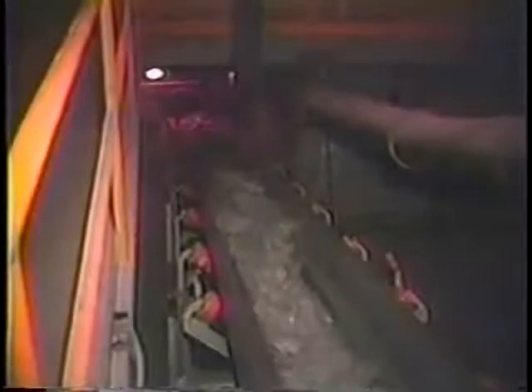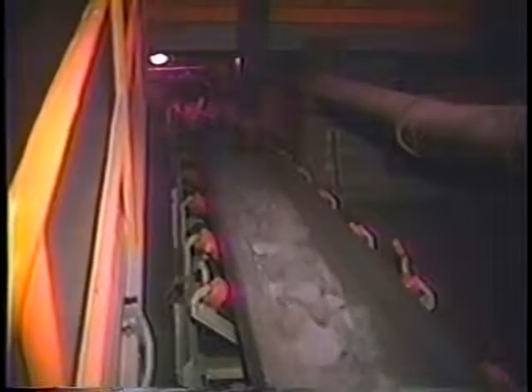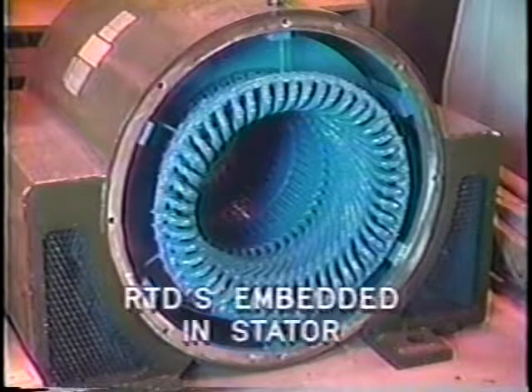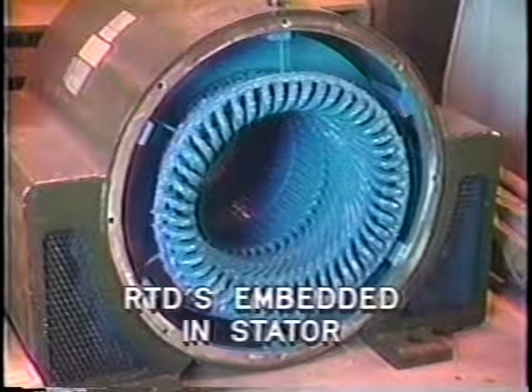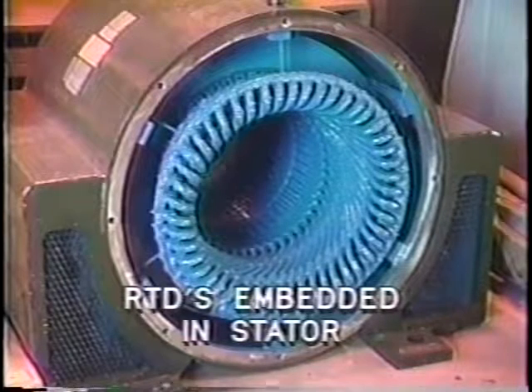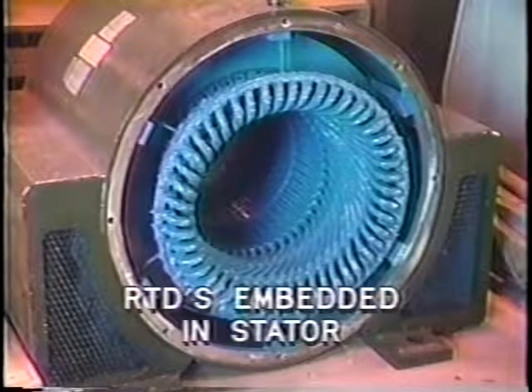When the ambient temperature around a motor is cold, it can carry overloads for a longer period of time. Hence, the overload protection will probably overprotect the motor and perhaps cause tripping unnecessarily. An improved method of protection against overheating directly measures the actual temperature of the winding and stator core. This method is used in motors above 500 horsepower and must be specified when the motor is purchased. When the motor is constructed, resistance temperature detectors, RTDs, are embedded in the stator slots along with the stator winding.